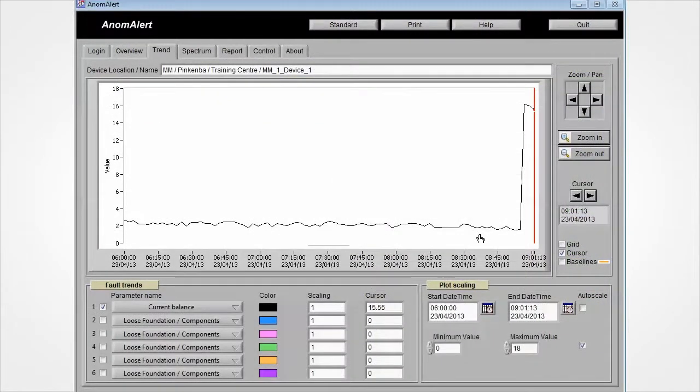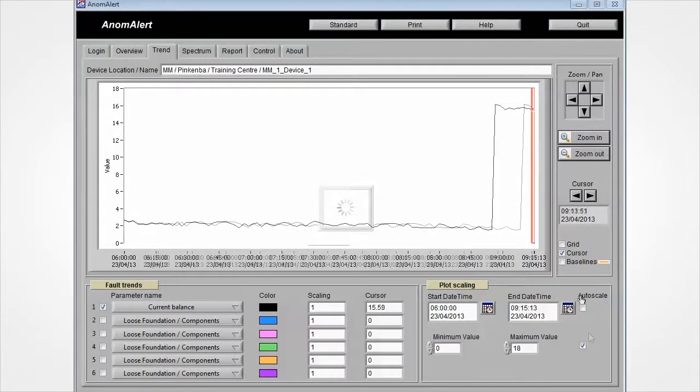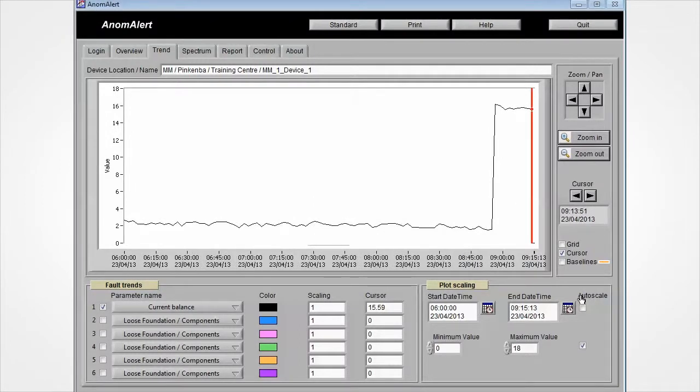On the trend tab, we can plot a trend line for the appropriate alarms. The plot shows a large rise in current imbalance at the time we introduce the turn fault into U phase.